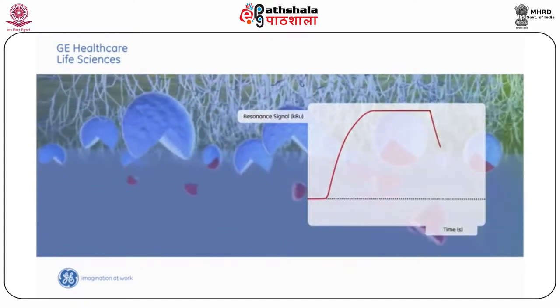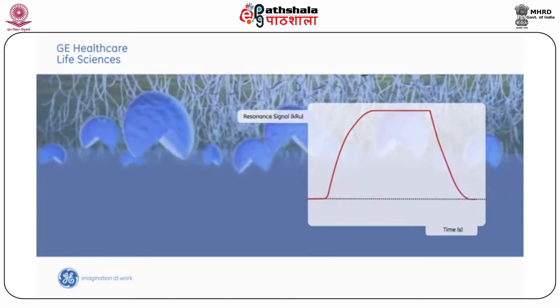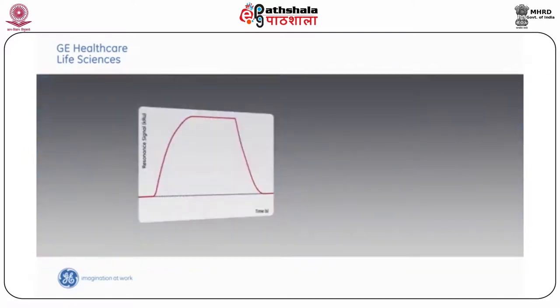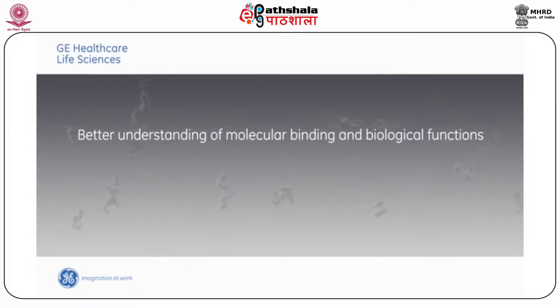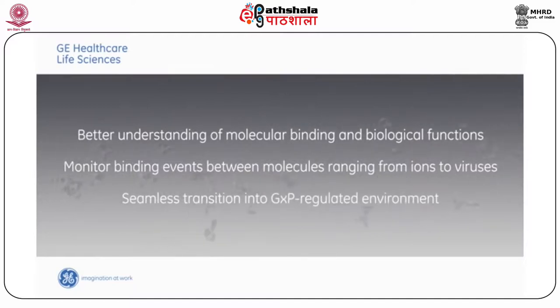Since light does not penetrate the sample, analyses can be performed on colored, turbid or opaque samples. From studying the shape of the sensorgram produced, binding yes or no, specificity, affinity, kinetics, and active binding concentration can be determined. The sensorgram provides real-time information about the entire interaction, meaning that in a single SPR experiment you obtain a wealth of information about your binding to understand the dynamics of the interaction or to quantify your analyte — all without using labels.